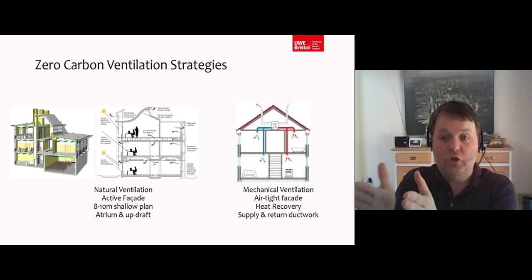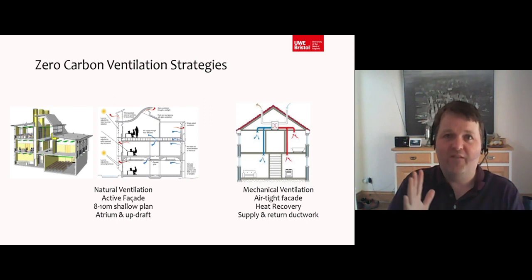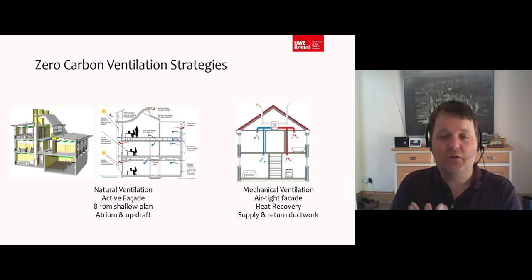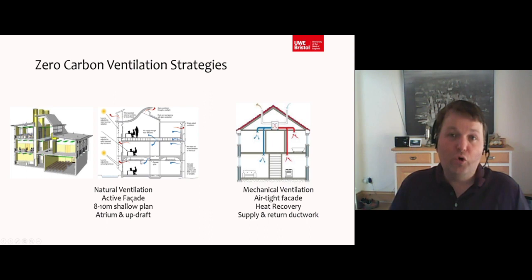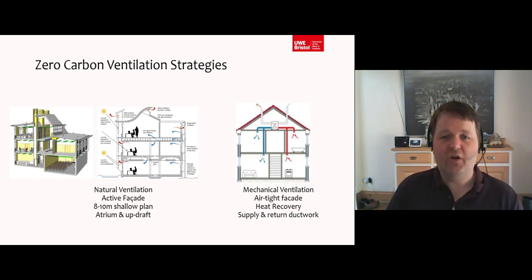The passive house system uses the sealed box method. So despite sometimes passive and active being denoted by one having a fan and one not, actually the passive house uses mechanical ventilation heat recovery and the sealed box method. It does not use natural ventilation. Sometimes people say, why not have something called mixed mode? Have both systems. And sometimes during the day it does mechanical, and then the mechanical turns off and the natural takes over. That could work in theory, but it's usually an economic barrier because you're now paying for two systems instead of one. So it's usually a cost issue rather than a technical issue in terms of making those things feasible.